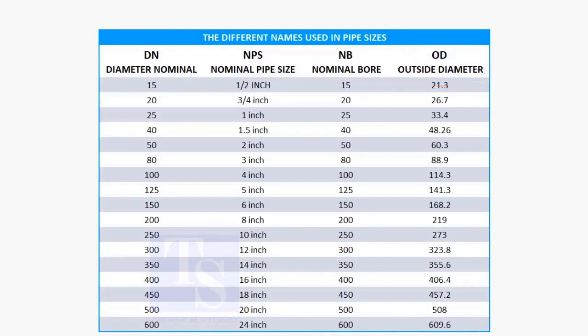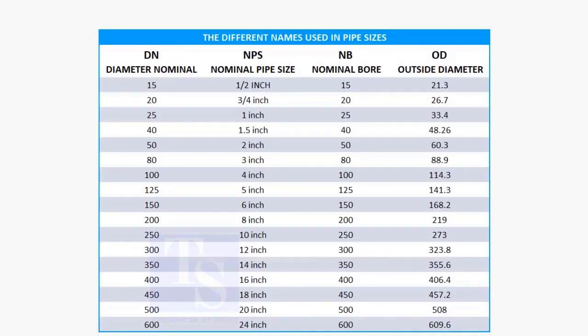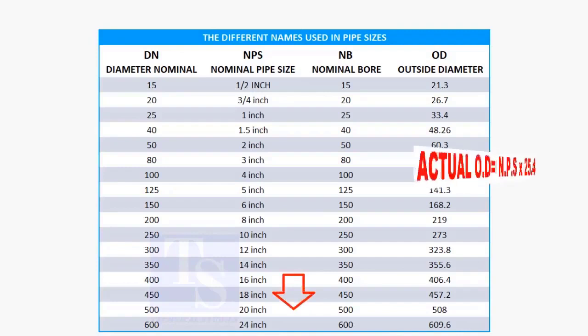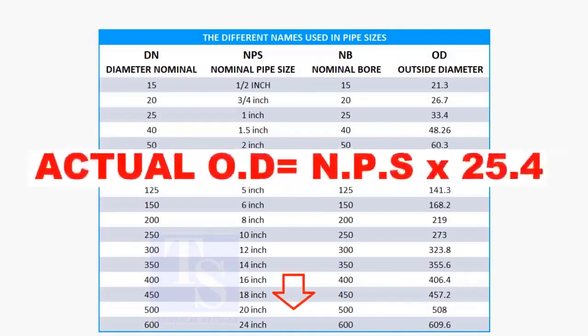But in the case of nominal pipe size, the NPS and actual pipe OD are different up to 12 inches. Up to 12 inch pipes, you may need to memorize the actual OD size. 14 inch and above, multiply the inch size by 25.4 to obtain the actual OD of the pipe.